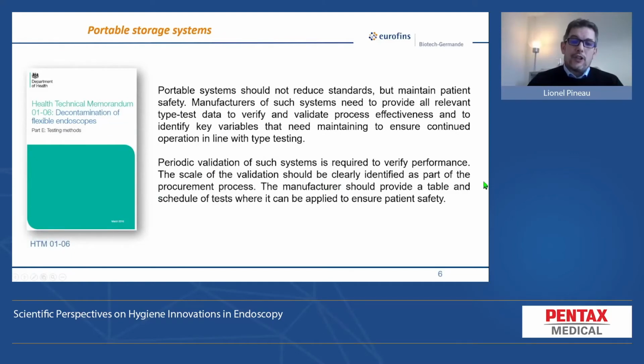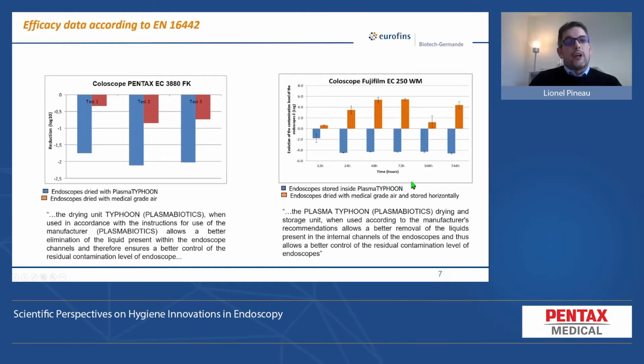As is stated in the French guideline published in 2016 and also in the HTM 0106, such systems shall be submitted to the same validation process as drying storage cabinets complying with the EN standard. And the need to submit this process is well accepted by all experts. So in fact, as it is mentioned in the HTM 0106 document, all systems intended to provide a safe environment for the endoscope during storage or intended to dry the endoscope need to be type tested to verify and validate their effectiveness. But we also need to validate periodically the performance of such systems, as it is mentioned in the EN standard. And it's exactly what we have done with the Plasma Typhoon system.